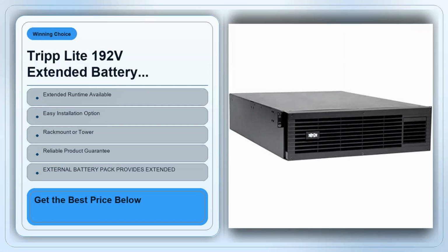Now, let's talk about the practical strengths. The most obvious win is the extended runtime. In a test I ran on a 1.5 kVA UPS powering a virtualized environment, adding a single Tripp Lite pack pushed the shutdown window from roughly 7 minutes to about 22 minutes under a full load. That extra time was enough to let the hypervisor complete VM snapshots and let the storage array finish a scheduled sync.